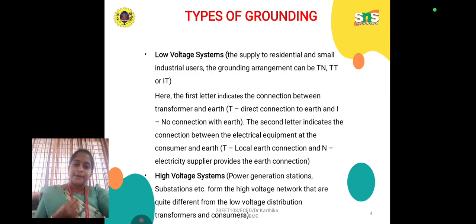Okay, and types of grounding, we have so many types. Particularly, we have two types. One is low voltage systems, another one is high voltage systems. Actually, we have some grounding arrangements based on government rules. Here we have TN, TT, and IT. Here the first letter T is direct connection to earth, and I is no connection with earth. In the second letter, T means local earth connection and N means the electricity supplier provides the earth connection.